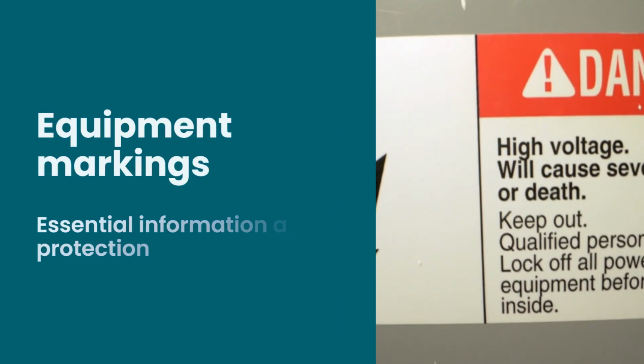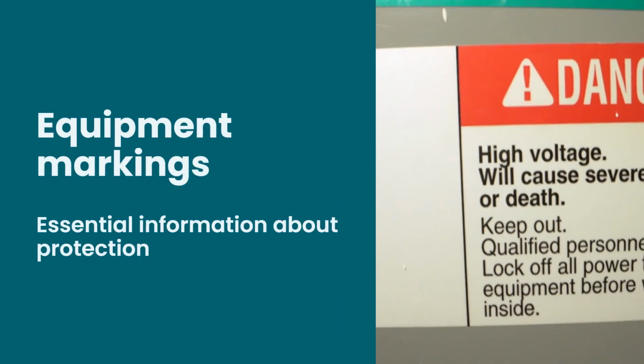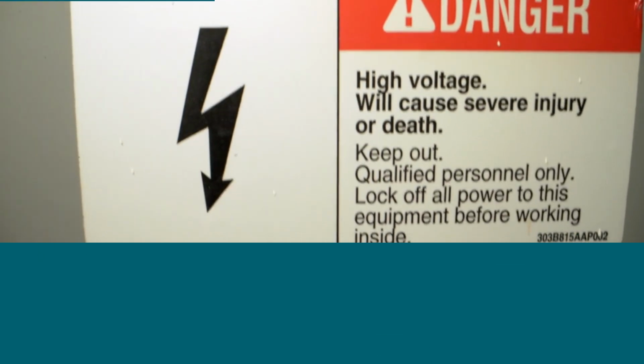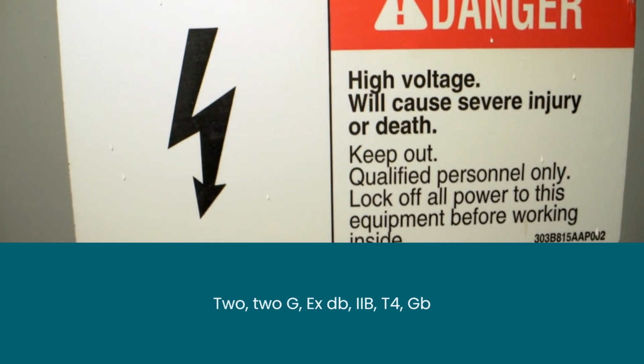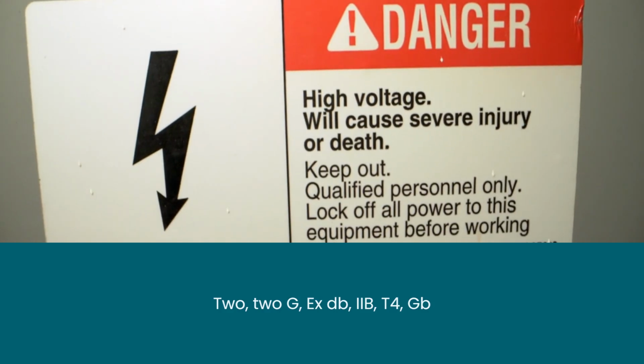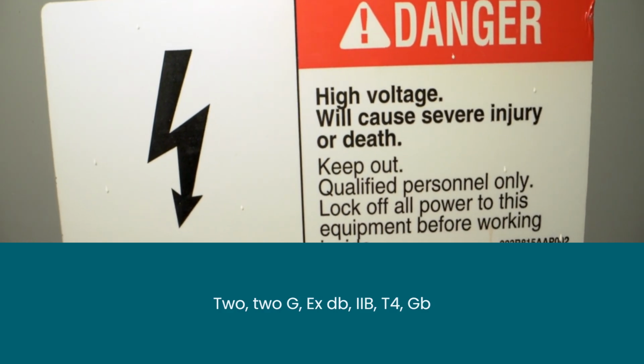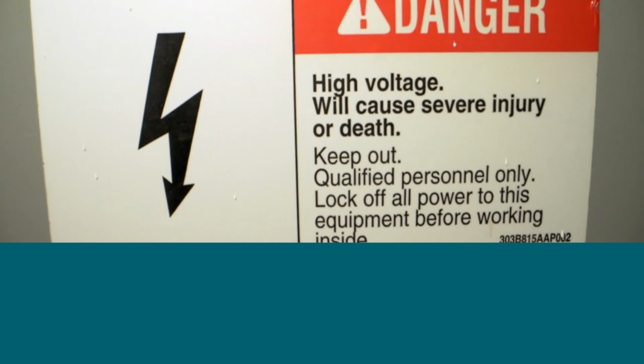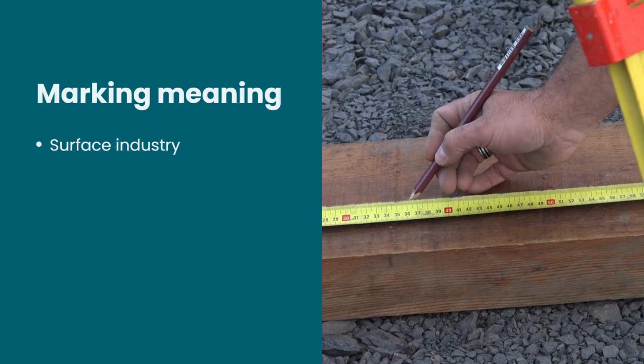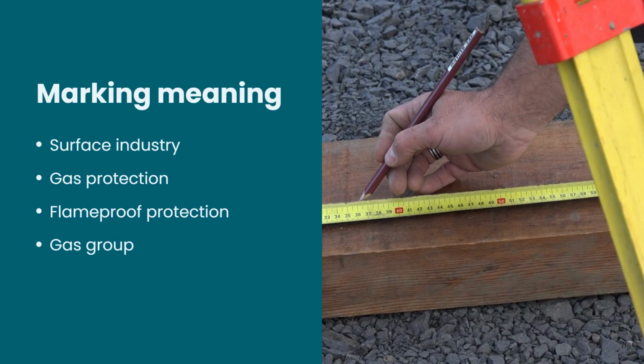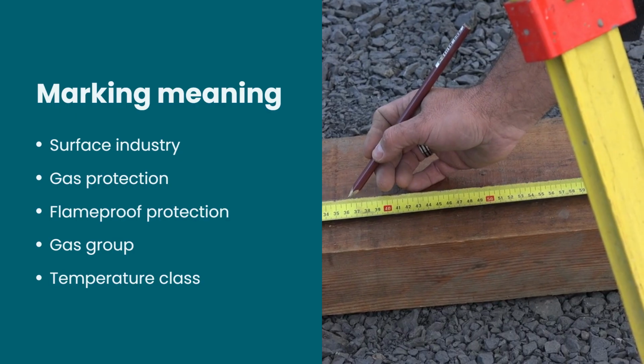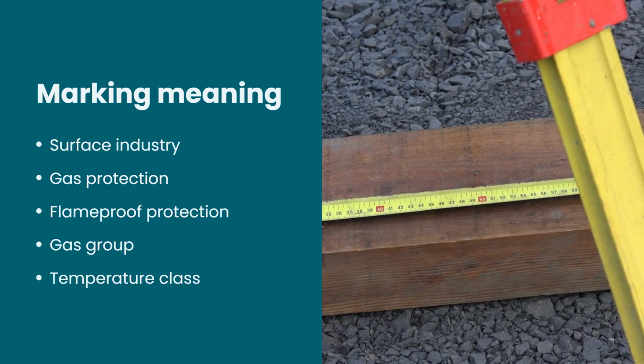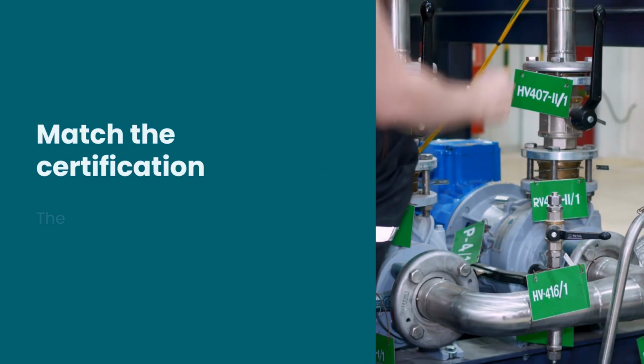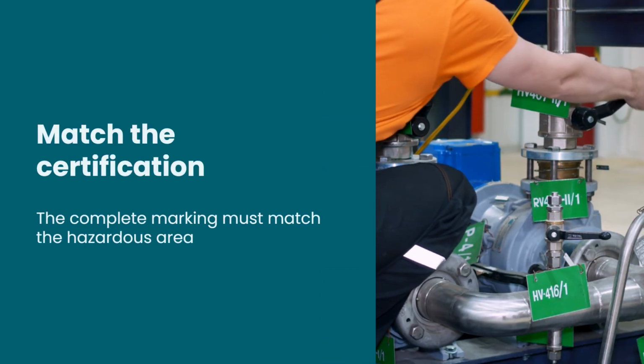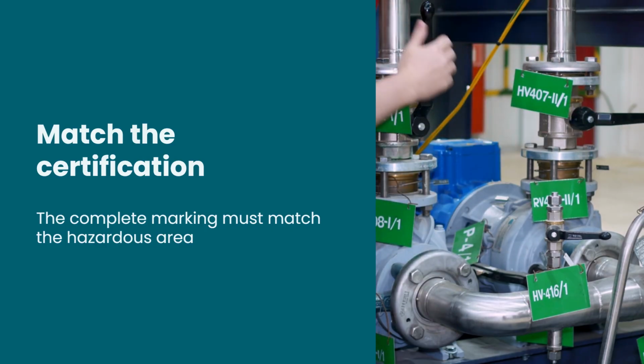ATEX markings provide essential information about equipment protection. For example, II 2G, Ex db, IIB, T4, Gb. The marking identifies surface industry equipment, gas protection, flame-proof protection, gas group, temperature class, and protection level. The complete marking must match the hazardous area, gas group, temperature class, and application.